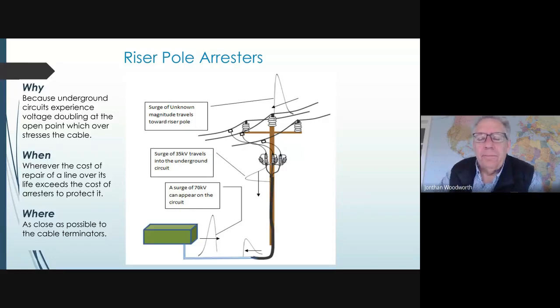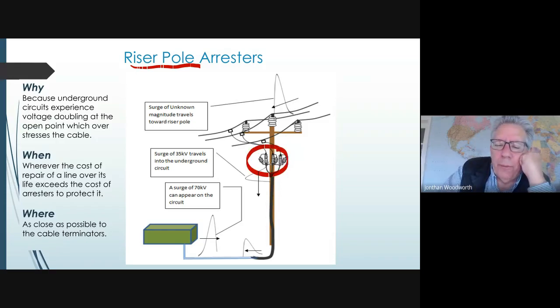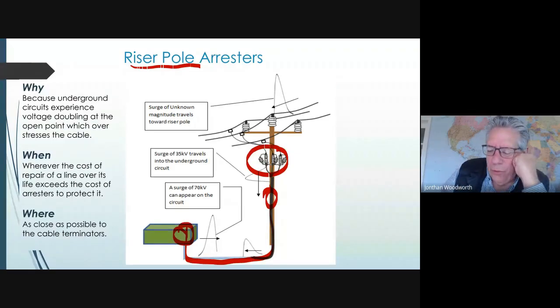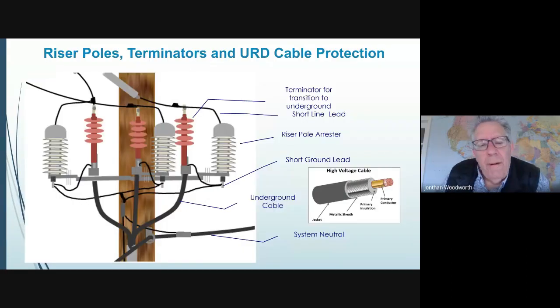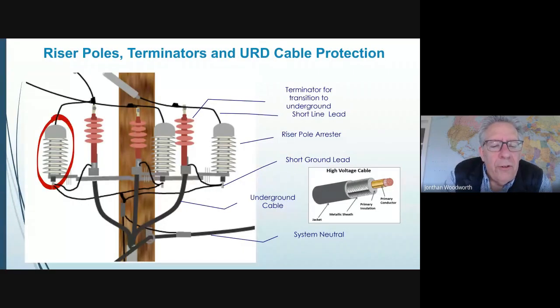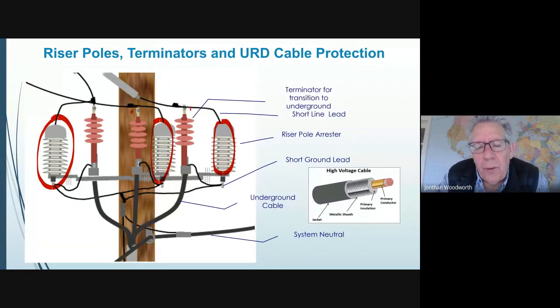I mentioned underground circuits. We call these riser poles. Sometimes they're called terminal poles. The arrestors are put here for protecting the cable, and they do give a little protection to the transformer at the other end too. But oftentimes arrestors are put right inside the transformers on the underground transformer. There's usually one arrestor for each phase. These are usually like the cream of the crop in arrestors because it's very hard to protect underground cables because of voltage doubling in the circuit.